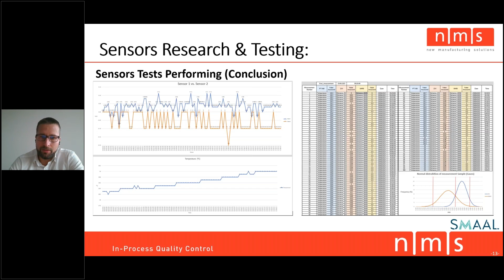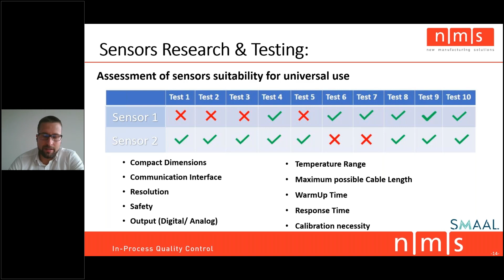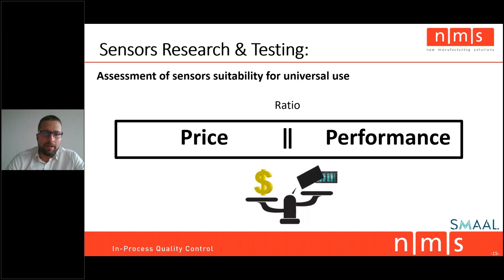As a summary, you receive a table testing whether a sensor passes or not. You also have to consider other aspects beyond accuracy, linearity, and repeatability, such as product dimensions, whether it's compact enough for the jigs, communication interface, resolution, and safety, since some laser sensors must keep measuring while operators move inside the jigs. Other factors include digital or analog outputs, temperature and working range, maximum possible length for large-scale measuring systems, warm-up time since it must work in real time, response time, calibration necessity, and finally price to performance ratio.